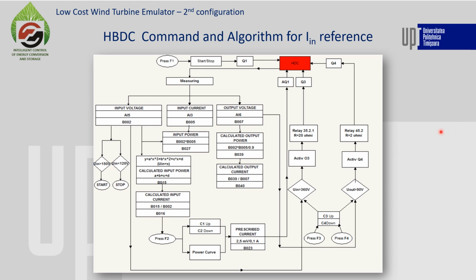So after the hybrid buck DC converter has started, the input voltage, input current, and output voltage are acquired by the intelligent relay from the HDC, which is the hybrid buck DC converter. First, on the left side, we can see that the input voltage is analyzed, and if its value is greater than 150 volts, the HDC will enter the operating state. If the value is under 120 volts, it will be stopped.